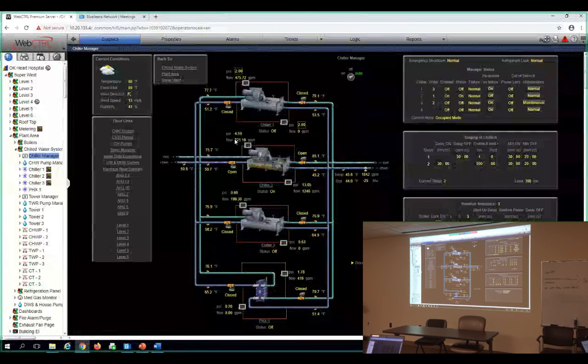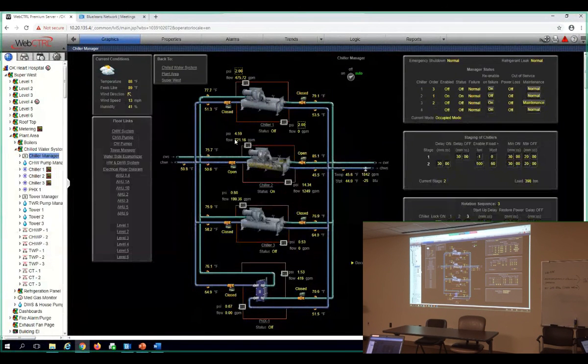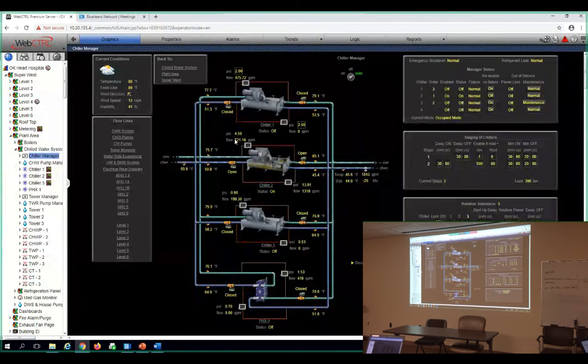Yes. And what it'll actually do, if we lock on one right now, it's going to start a pump, it's going to open up, it's going to start a tower pump. Chill water pump is based on pressure on the building side, but it will start a tower pump and open a tower. So we can only run one pump on your towers. We're blowing apart pipe when I try to run two during that.